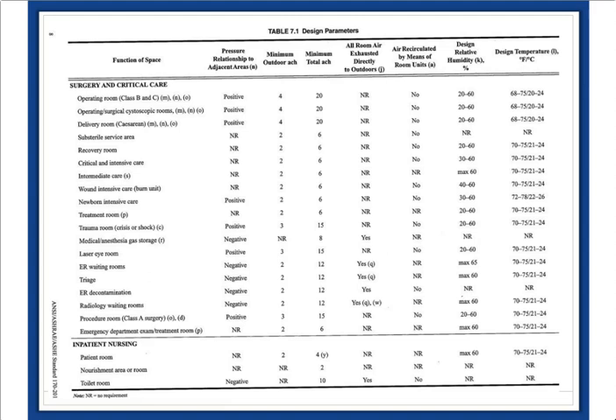This table provides information about what the pressure of that space should be relative to its adjacent spaces, the minimum number of outside air changes we should design for, the total number of air changes, and it would answer the question: should all air be exhausted directly to the outside?